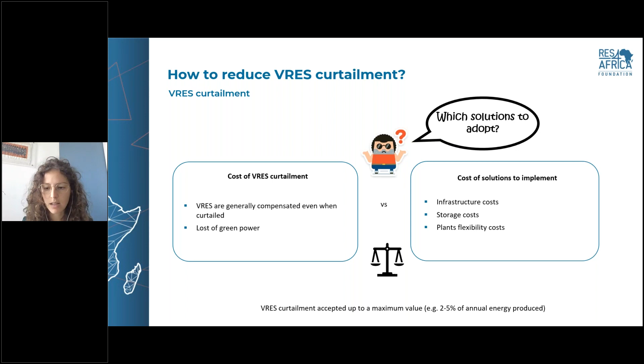Here you have an image representing what the risk of overgeneration means. We have the blue curve, that is the load, and we speak of net load when we consider the fact that the load is decreased thanks to the production of renewables. The problem is that if this net load is very low, and if we have constraints related, for example, to import power that was already paid for and needs to be dispatched, or constraints related to the minimum amount of dispatchable sources, we may have cases of overgeneration, that is the green curve. Basically, the generation cannot be equal to the load, but will be higher. A solution in this case is represented by the blue curve, where pump systems absorb energy during the moment of overgeneration, decreasing in this way the overgeneration that at the end translates into curtailment.